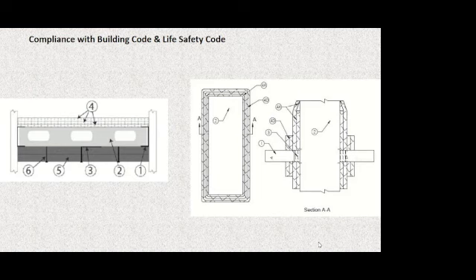We're going to talk about a lot of the things that are done in the fire rated duct industry that literally are worse than doing nothing at all. Because what it takes when you get into the designs to provide equivalent fire resistance to those drywall assemblies that are prescribed by the code, we're going to see something very different than probably what you're used to seeing. I don't know how many of you have seen minimum 2-inch pressure class SMACNA duct with one layer of some kind of fire product on it. And somebody's telling you that that's fire rated for 2 hours. And I'm here to tell you there were a whole bunch of mistakes made along the way to that concept.